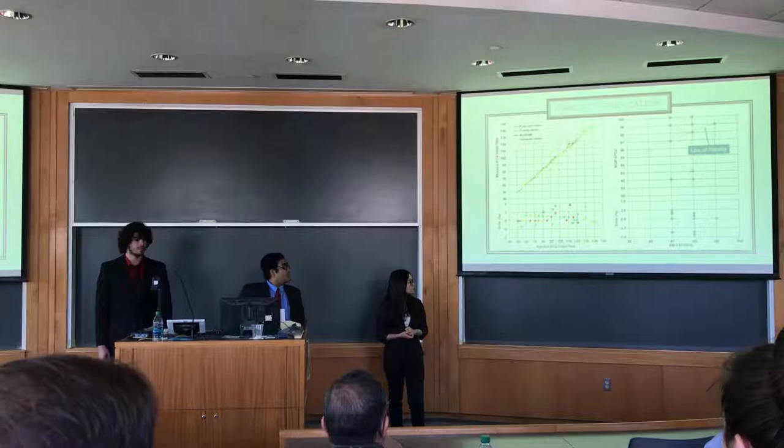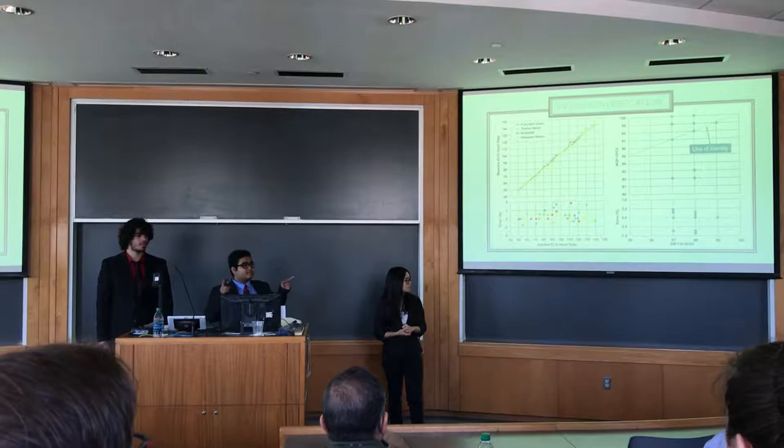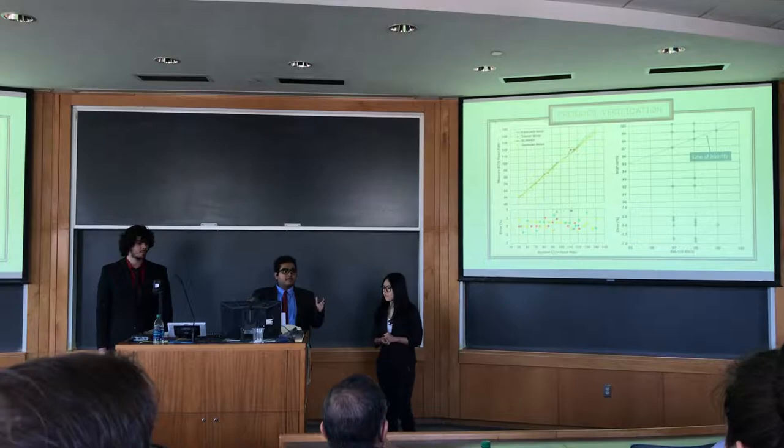Also, to measure the accuracy of the blood oxygen level, we bought an FDA-approved pulse oximeter, SN10. We collected from 2 fingers of the same person at the same time, one to the SN10, the other to our device, and we collected the blood oxygen level and plotted them against each other. Again, you can see a linear trend, with error between plus minus 7%.